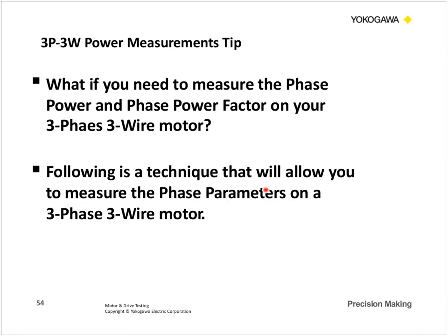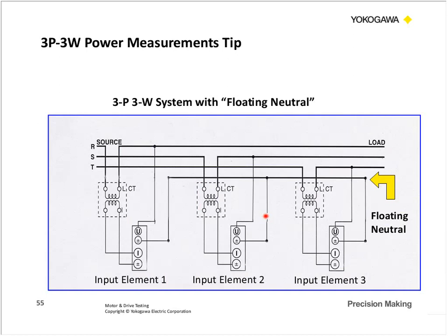So what if you need to measure the phase power and the phase power factor on a three-phase, three-wire motor? I'm going to give you a technique to help you do that measurement. If we have a motor, say a synchronous motor, we can create what we call a floating neutral. Instead of measuring these voltages line to line, we can tie the low side of the voltage together on each of the input elements and just let it float. It does not go anyplace. It's not grounded. It's just floating.